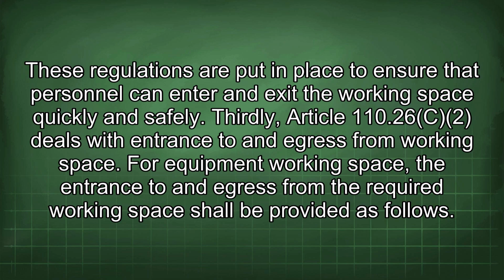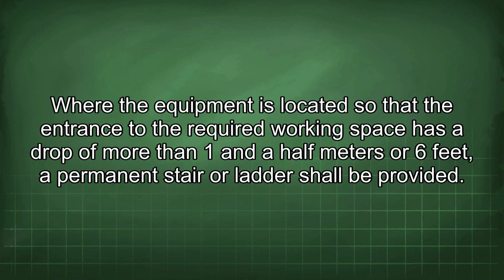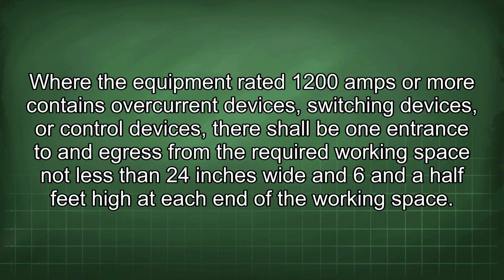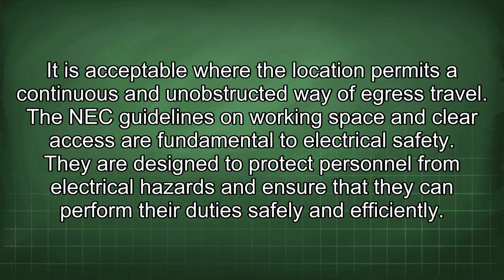Thirdly, Article 110.26c2 deals with entrance to and egress from working space. For equipment working space, the entrance to and egress from the required working space shall be provided as follows. Where the equipment is located so that the entrance to the required working space has a drop of more than 1.5 meters or 6 feet, a permanent stair or ladder shall be provided. Where equipment rated 1200 amps or more contains overcurrent devices, switching devices, or control devices, there shall be one entrance to and egress from the required working space not less than 24 inches wide and 6.5 feet high at each end of the working space. It is acceptable where the location permits a continuous and unobstructed way of egress travel.